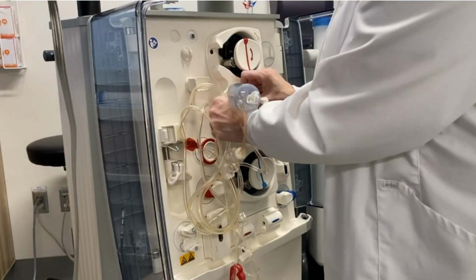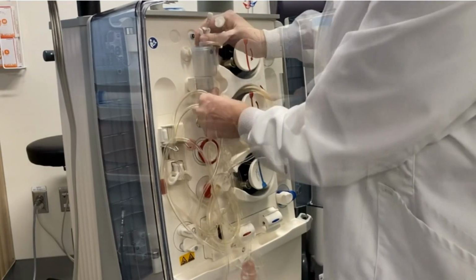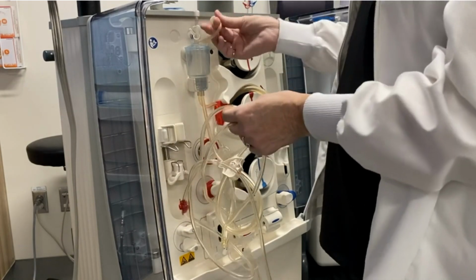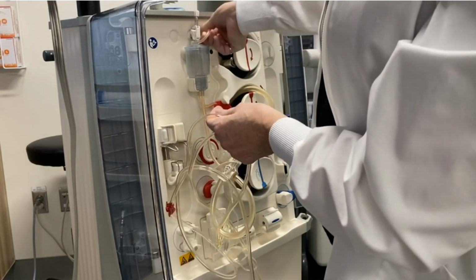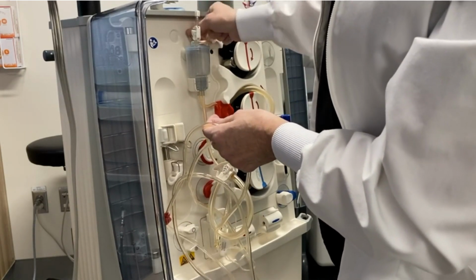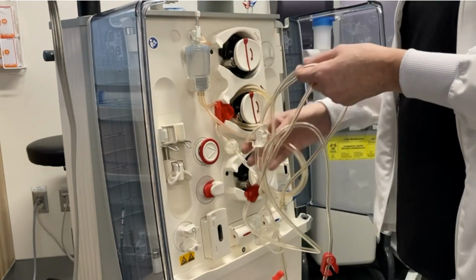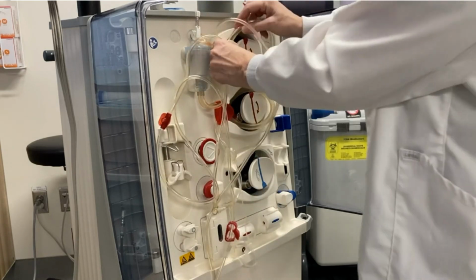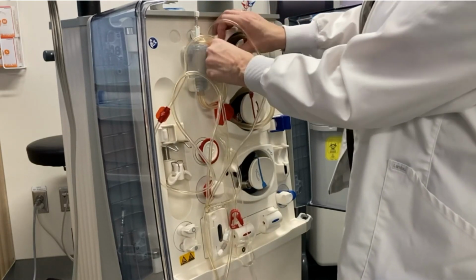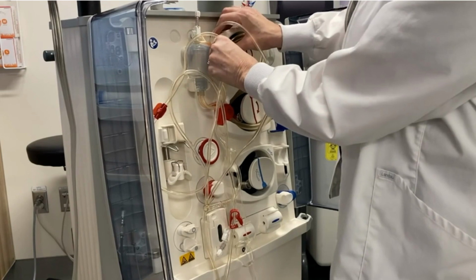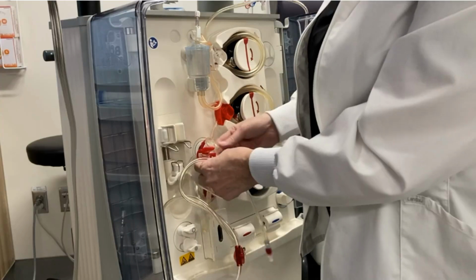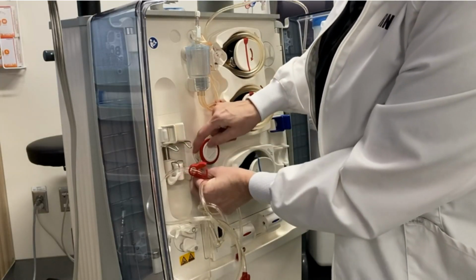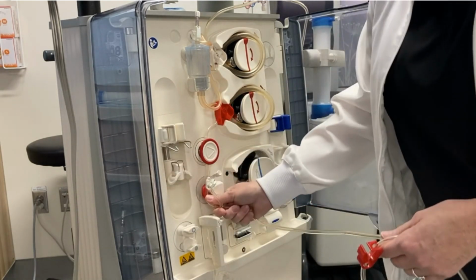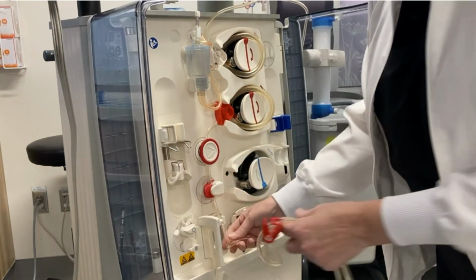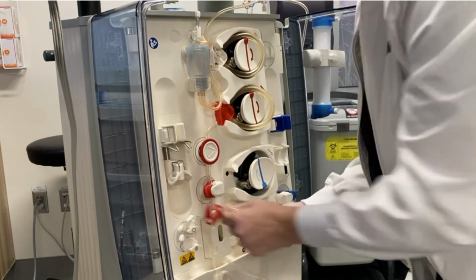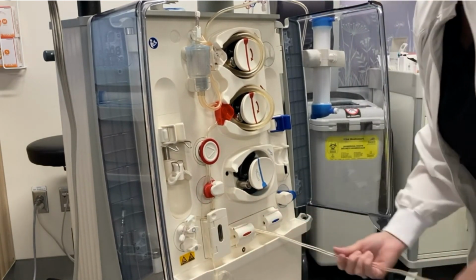I'm putting in the arterial pump segment, the arterial chamber, and attaching the arterial chamber transducer. And then I'm going to put in the single needle pump segment. Next, I'm going to put in the arterial pressure dome, the arterial clamp, and the cuvette, and the arterial temperature monitor.